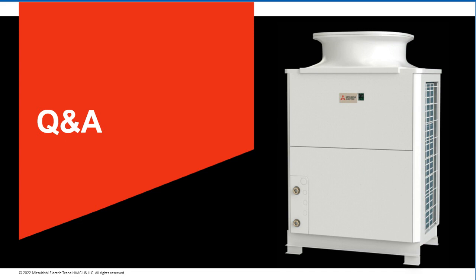All right. Oh, so this is a different question. What are the typical COPs when using this product in mild outdoor air temperatures, such as 47 degrees Fahrenheit? Yeah, so COP can range drastically with ambient temperature, but in milder temps you're going to see anywhere from 3.5 all the way up to about 4.5 for a COP out of the product. And then as you get lower, one of the benefits of CO2 is it can maintain a little bit higher COP into those lower ambient temps. So you can see a COP of 1.5 even at zero to negative conditions. Okay. Any additional thoughts?